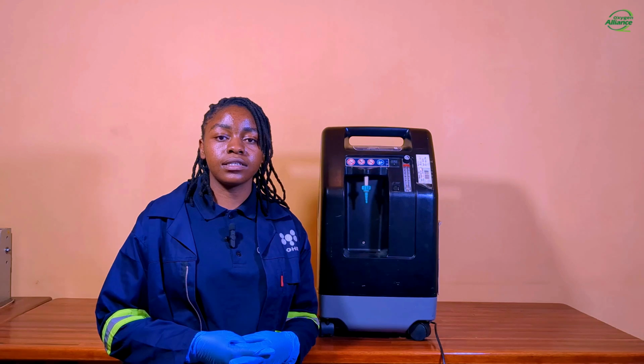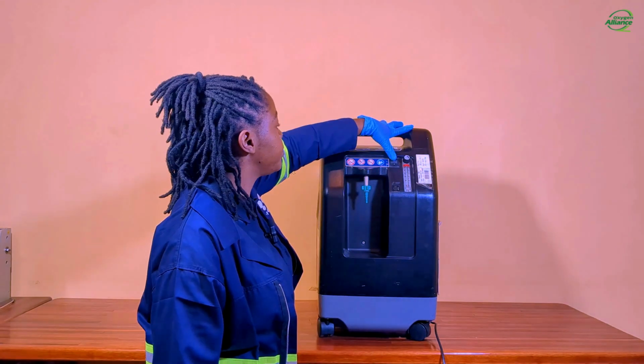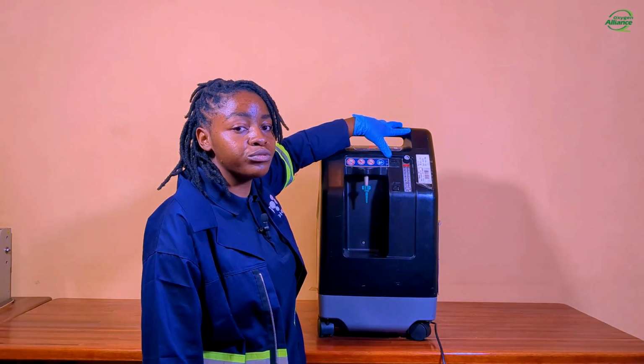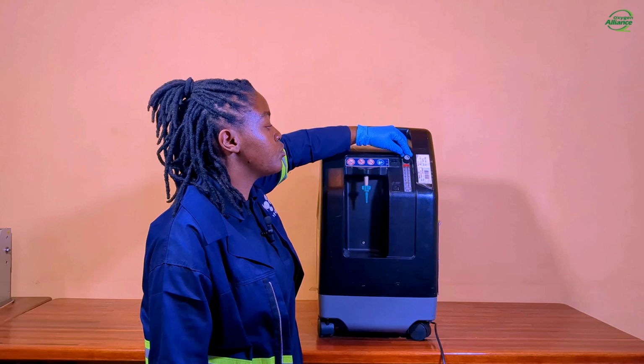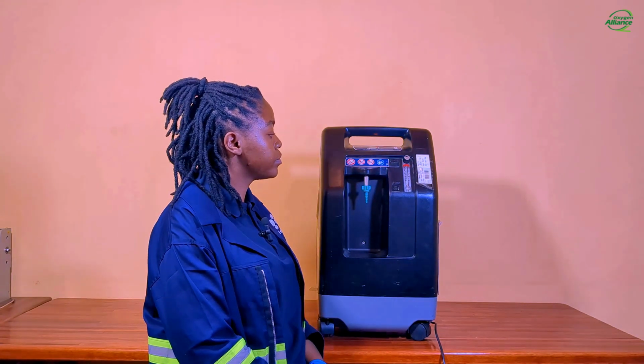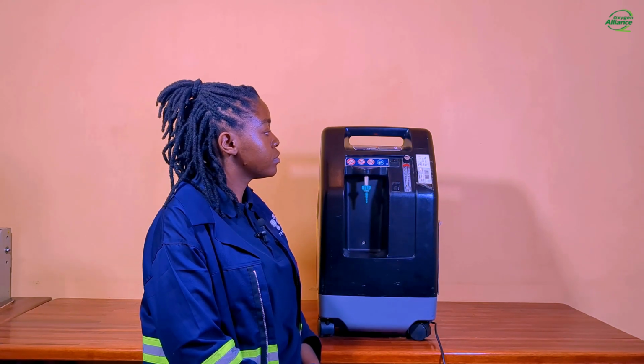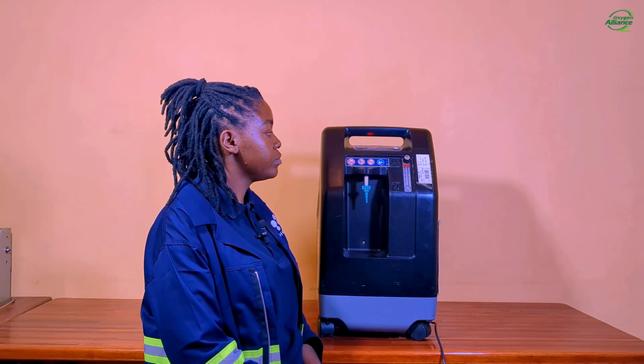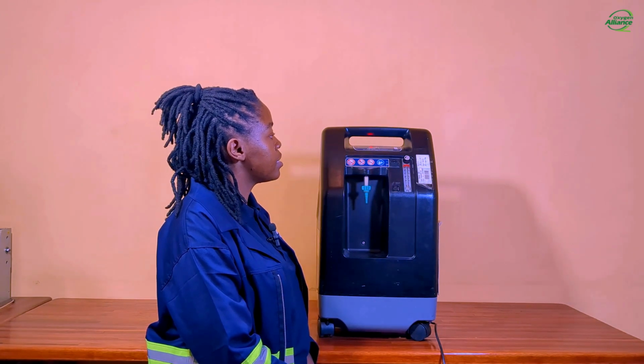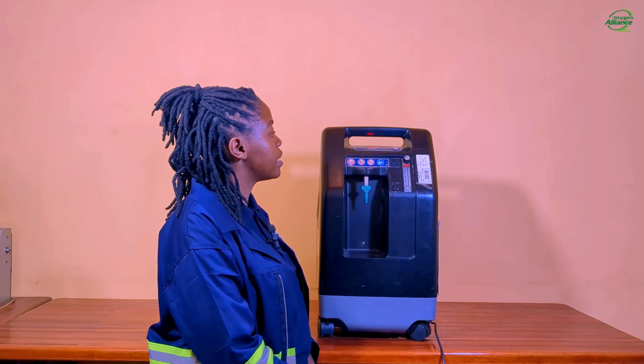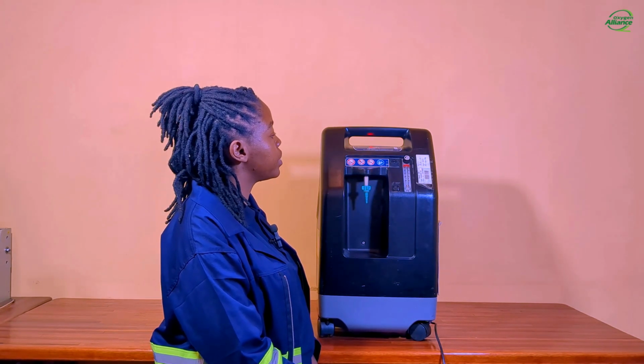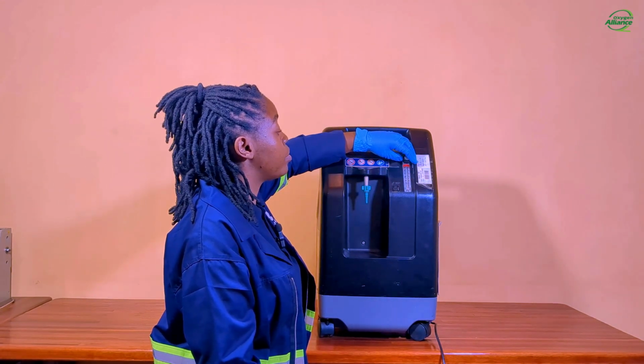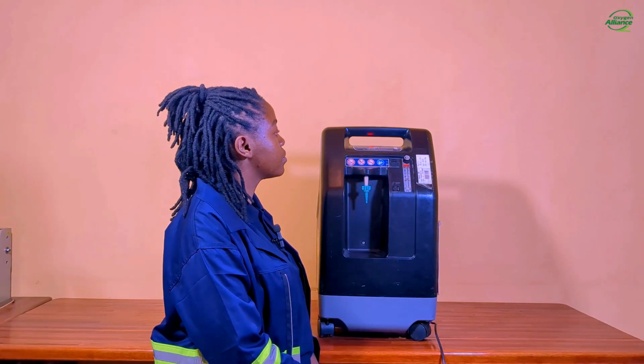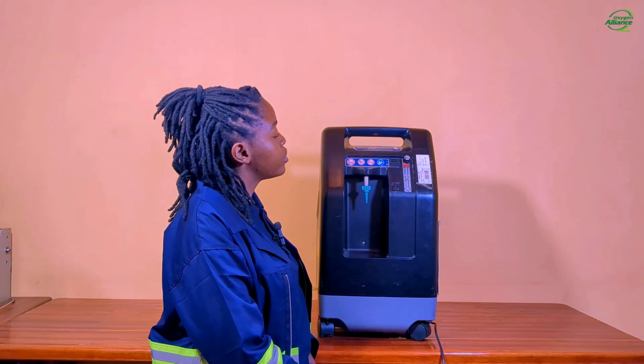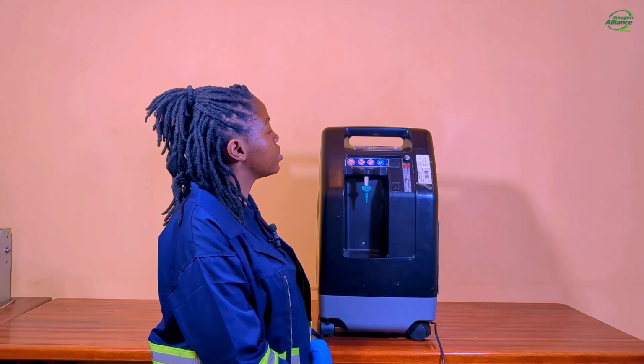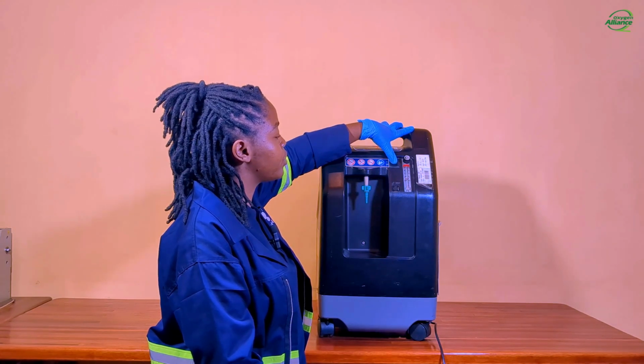So to demonstrate this alarm, I will first turn on my concentrator. Then I will reduce the flow to 0 liters per minute, which will cause an obstruction. So as you can see, the service indicator light has turned on, which is indicating an obstruction within the system. And to remove it, I'll simply just increase the flow rate to above 2 liters per minute. So with that done, the service indicator light has turned off. So I'll turn off the concentrator.